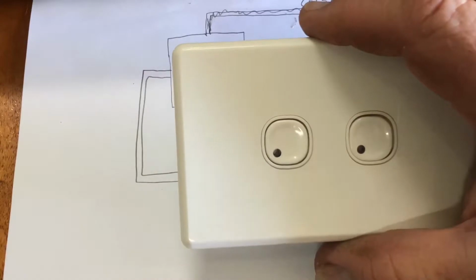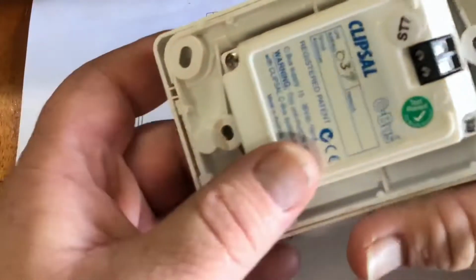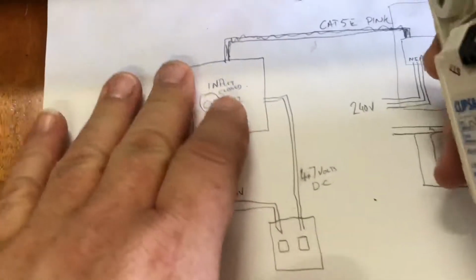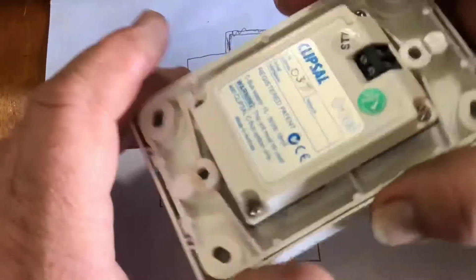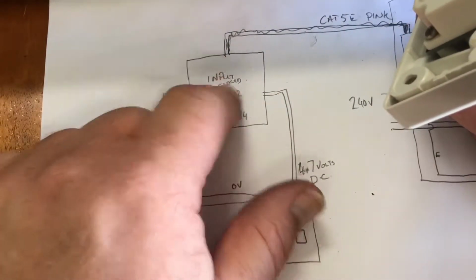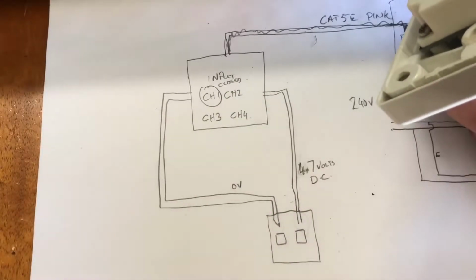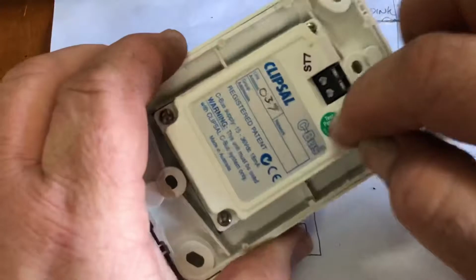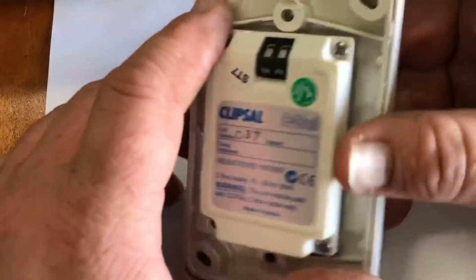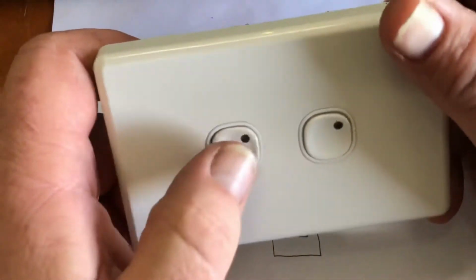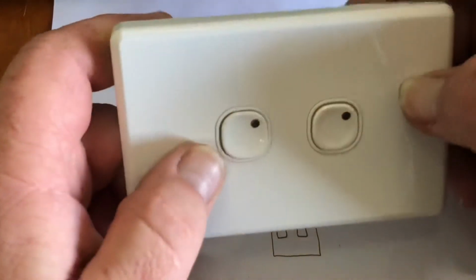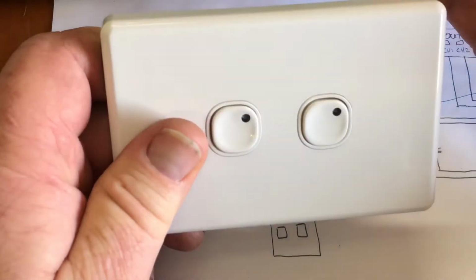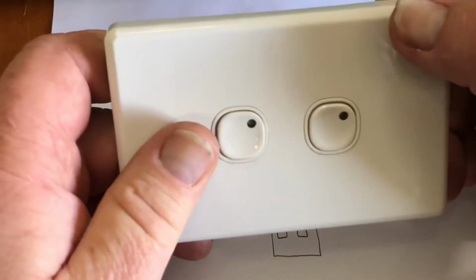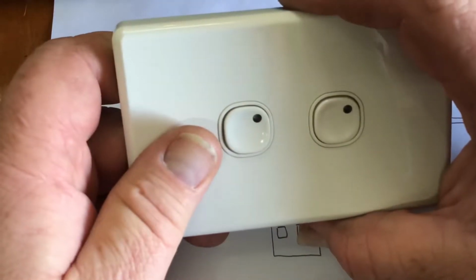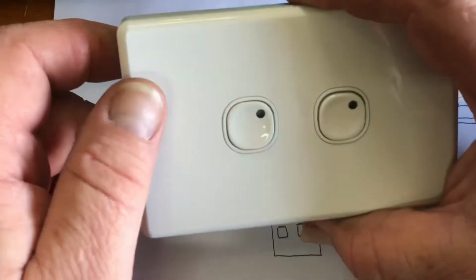So here's our new gang plate that we're going to program up and replace that existing switch. This is an input device on its own, so it doesn't need this input device here. Therefore, once we've eliminated the 4 channels on this input device, that input device can be taken off the CBus network. This being an input device on its own, we've got to program it to tell it what we want it to do. So this gang switches, we want this one to say turn the outside lights on for 15 minutes and then turn off, unless you press a button to turn it off again. So that will be a timed delay. And this one will be just a straight on and off for the laundry light.